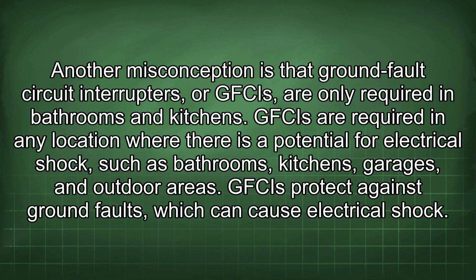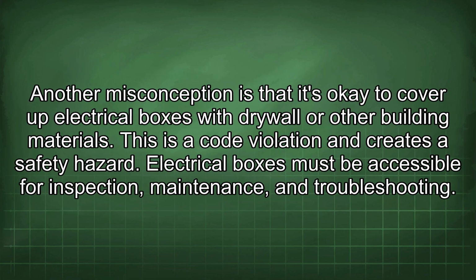Another misconception is that ground fault circuit interrupters, or GFCIs, are only required in bathrooms and kitchens. GFCIs are required in any location where there is a potential for electrical shock, such as bathrooms, kitchens, garages, and outdoor areas. GFCIs protect against ground faults, which can cause electrical shock. Another misconception is that it's okay to cover up electrical boxes with drywall or other building materials. This is a code violation and creates a safety hazard. Electrical boxes must be accessible for inspection, maintenance, and troubleshooting.